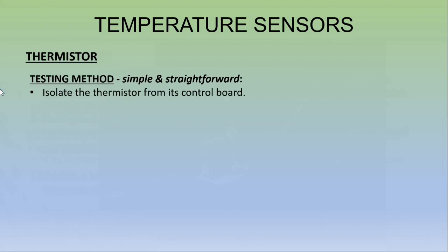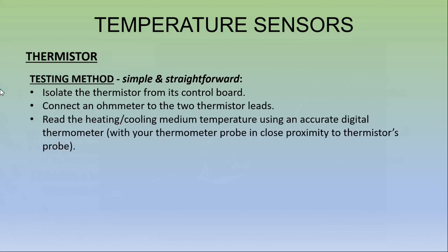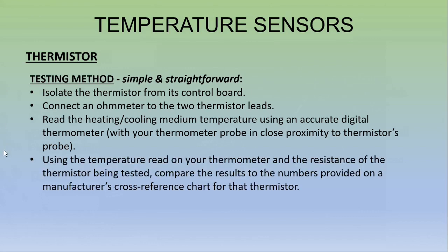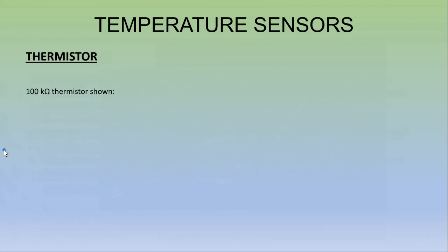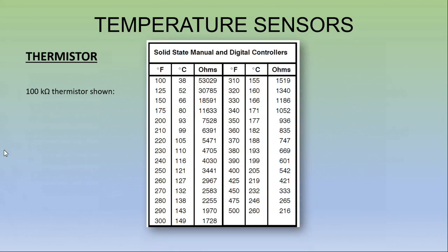Isolate the thermistor from its control board, connect an ohm meter to the two thermistor leads, read the heating or cooling medium temperature using an accurate digital thermometer. With your thermometer probe in close proximity to the thermistor's probe, using the temperature read on your thermometer and the resistance of the thermistor being tested, compare the results to the numbers provided on a manufacturer's cross-reference chart for that thermistor. Here's an example of one of those charts, and actually this example uses a very commonly used thermistor.